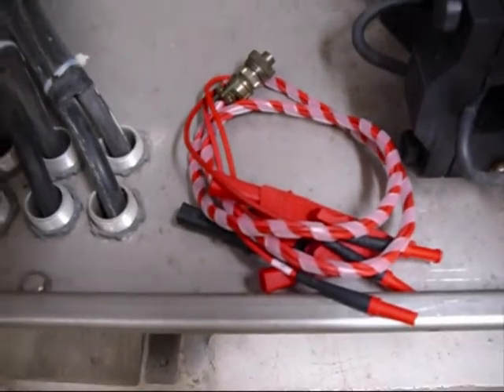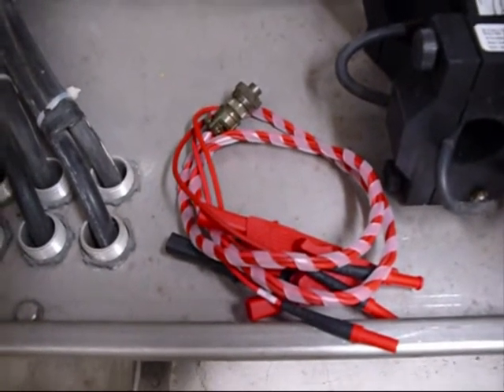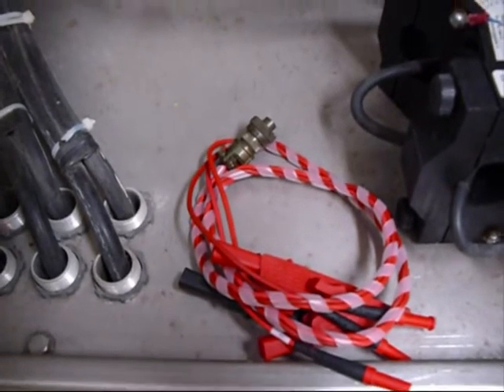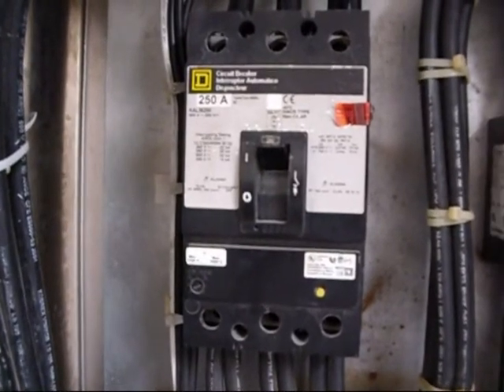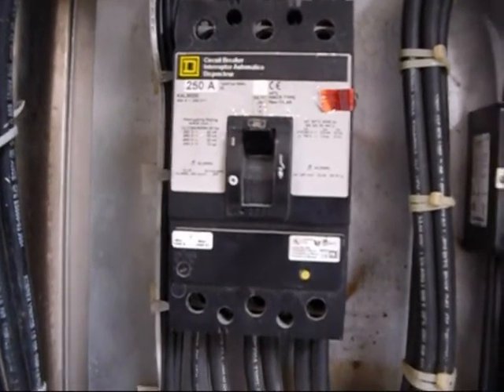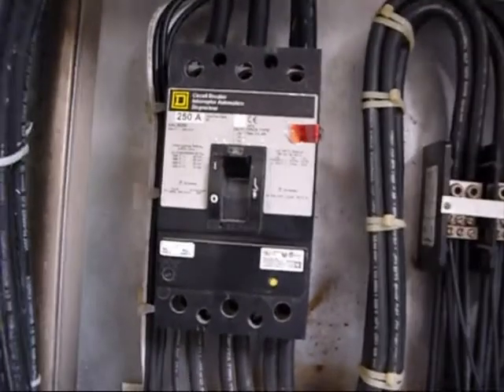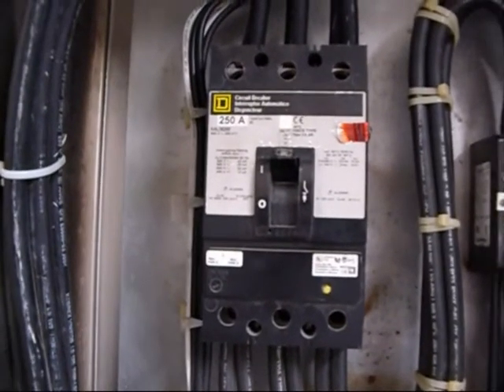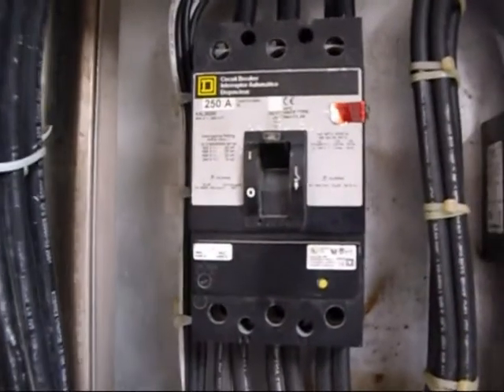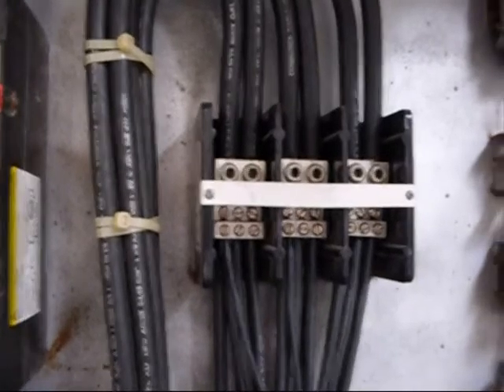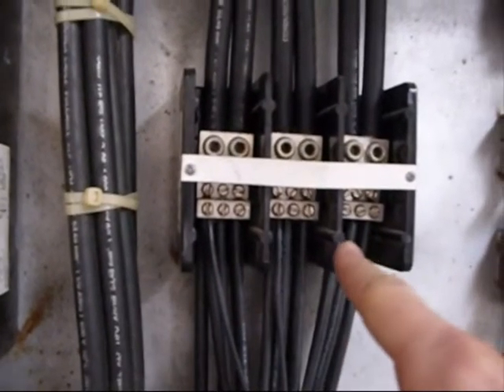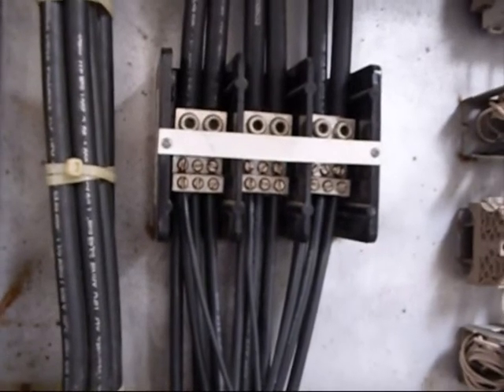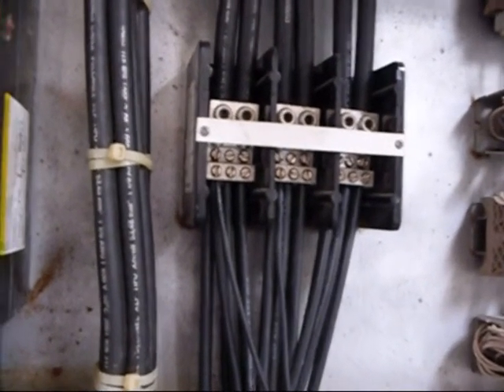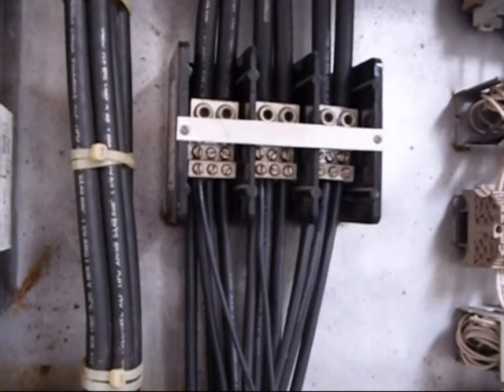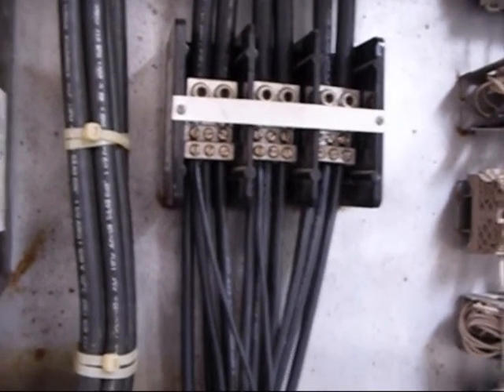Our next stage in the process is to fit the voltage connections. It's really important that you isolate the power before you connect the voltages. In this case, this would be done with this switch. So what we would do is we would isolate this. Now, your voltage connections come with several types of connection. We can connect into terminals or we can clip. You've been supplied with alligator clips. What we're going to do in this case, we're going to connect the alligator clip to these connections on the incoming supply. Note that we're using the common supply. It doesn't make any difference whether we connect to the common supply or the individual cable going to the machine.